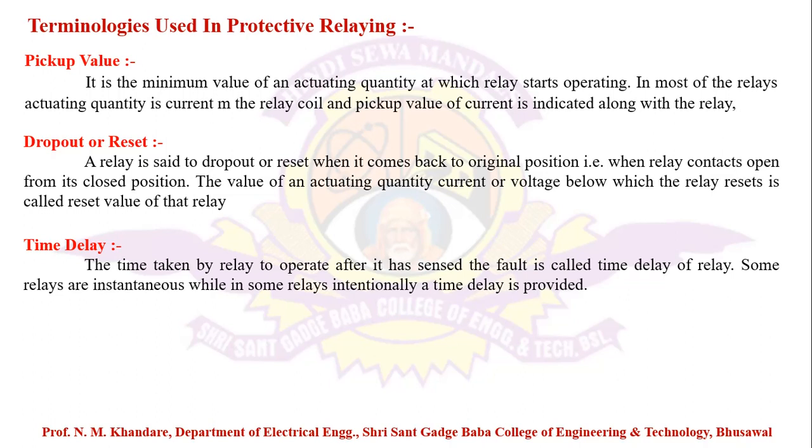To avoid this, we give some delay of operation to the relay, and that is called the time delay of the relay. Some relays are instantaneous, while in some relays a time delay is intentionally provided simply to avoid unnecessary operation of the relay at switching operations.